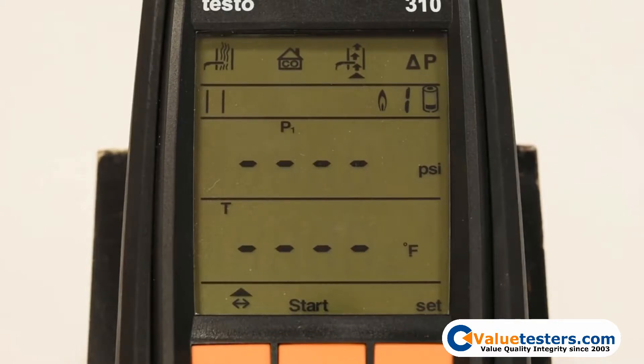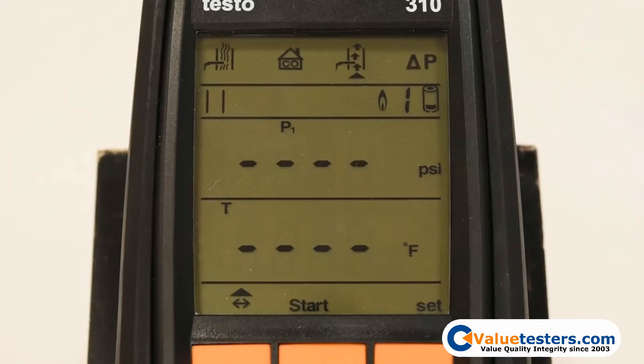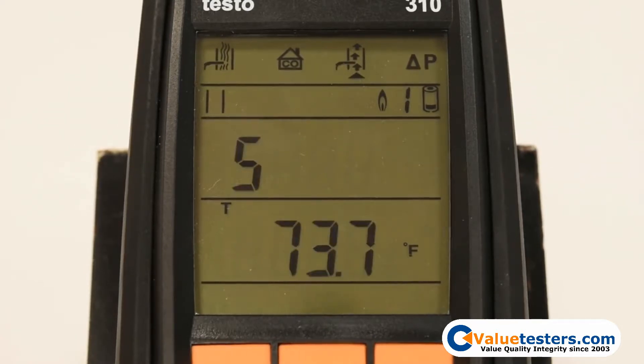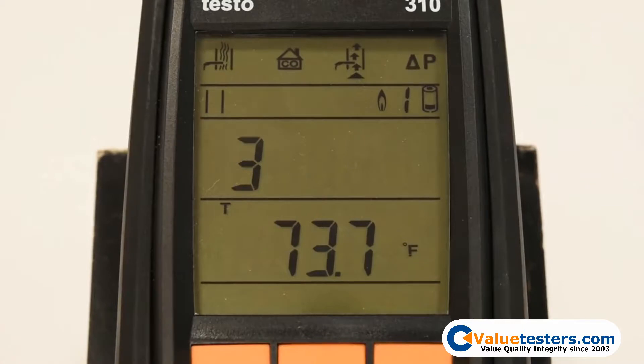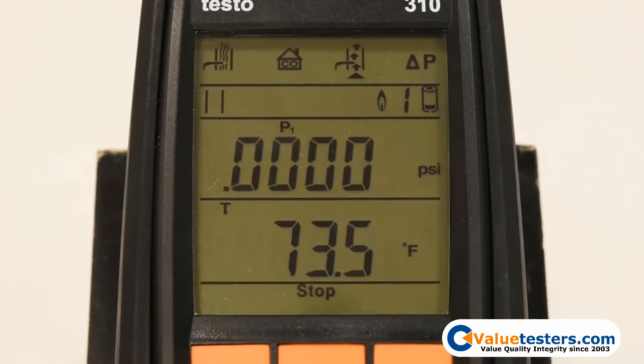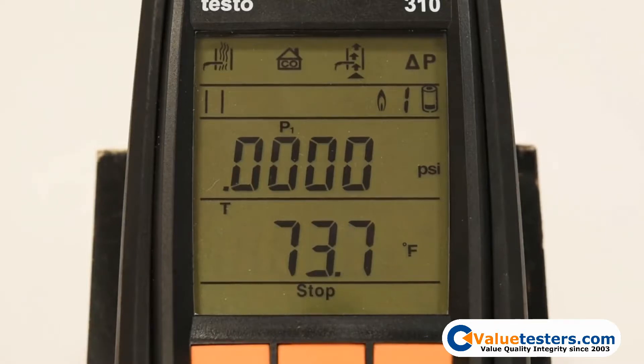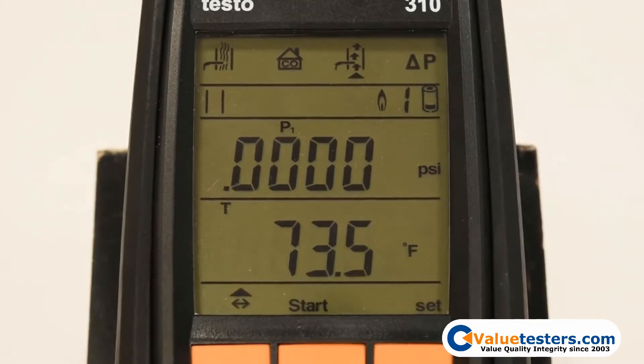When selecting draft measurement, it is important to start the test with your flue gas probe outside of the flue. You can then start the measurement using the center orange button, and a draft zeroing countdown will appear on screen. Make sure that the probe remains still during this countdown to achieve a proper zeroing. You can stop the measurement by pressing the center orange button again.